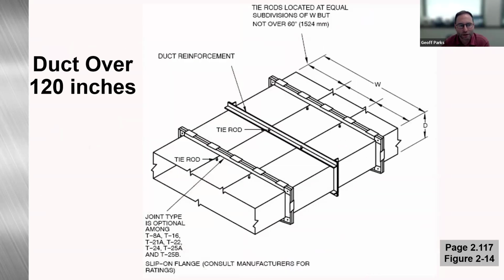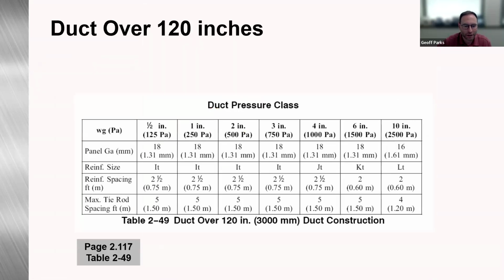So the main thing to point out when you're constructing duct over 120 is that tie rods are required at each joint and each intermediate duct reinforcement. That's a little different than duct that's less than 120, where, depending on what construction table you're looking at, it would tell you if you need a tie rod or not. But when you're building over 120, tie rods are a requirement at each of those scenarios.